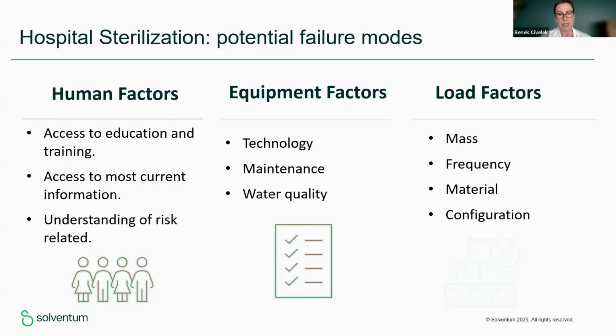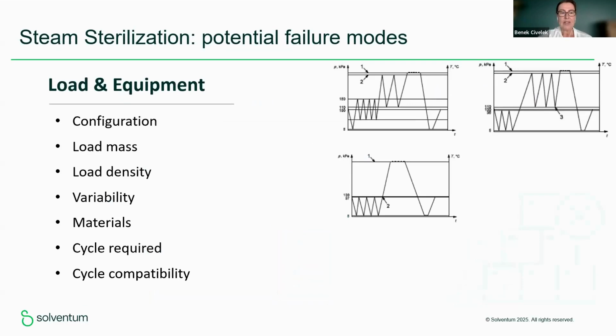And load is always an important point, because the configuration, the material, and cycle compatibility also reflect on sterilization success. There are steam sterilization failures. Steam sterilization is the one that we are using the most. For that reason, we have to know how it works, the right cycles and everything. But at the same time, we have to acknowledge that the load we put inside is of great importance, because steam works like this: first the vacuum, all the air is out of the chamber, and then we expect saturated steam inside every load. So there should be some really good space in between the load. So the density, the materials, and the right cycle have importance in steam sterilization success.